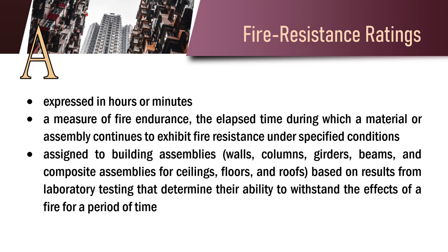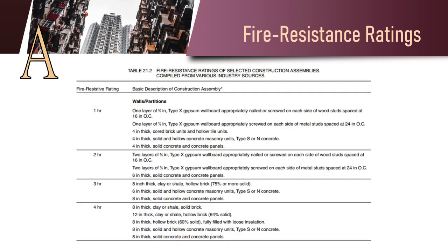based on results from laboratory testing that determine their ability to withstand the effects of a fire for a period of time. Table 21.2 shows the fire resistance ratings of selected construction assemblies compiled from various industry sources. The first column consists of the fire resistive rating, and corresponding to each of them are the basic description of construction assembly. This table includes the fire resistive rating for walls and or partitions, floors and or ceilings, steel columns, and doors, which include fire door, frame, hardware, and other accessories.